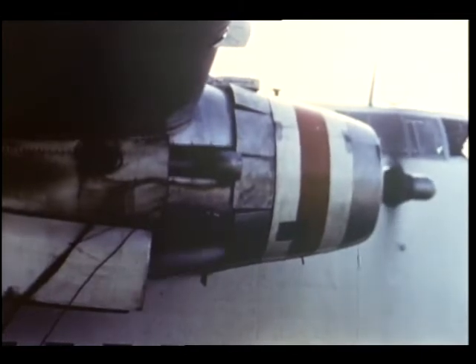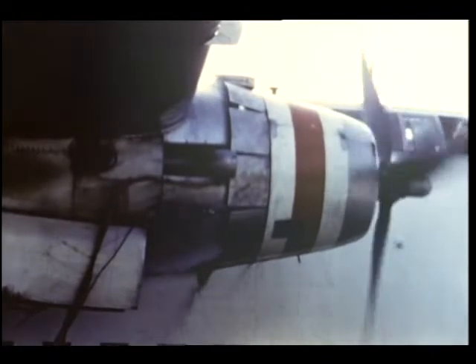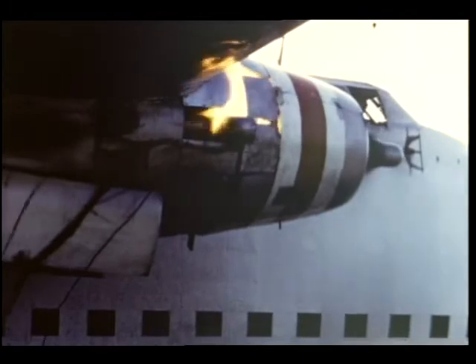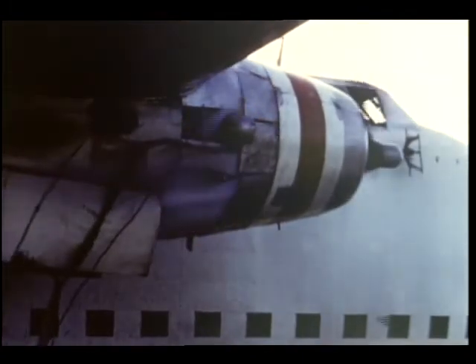The effectiveness of the water spray in preventing ignition on the hot exhaust is demonstrated by the rapidity with which a continuously fed oil fire burning from the exhaust system is extinguished by the water spray. Notice how the application of the water spray extinguishes the fire almost at once.